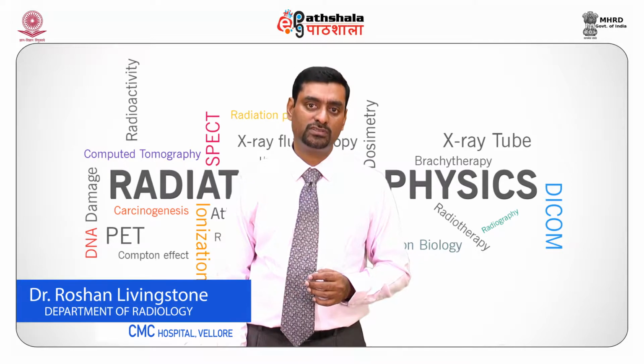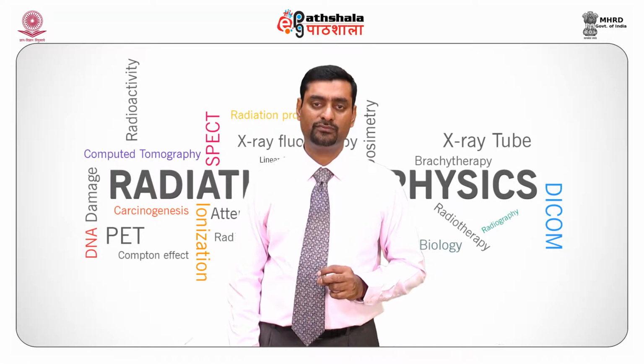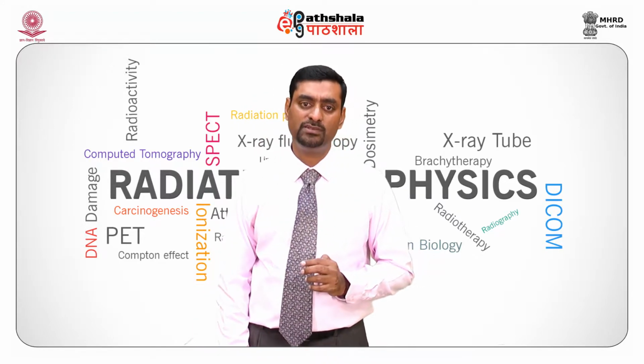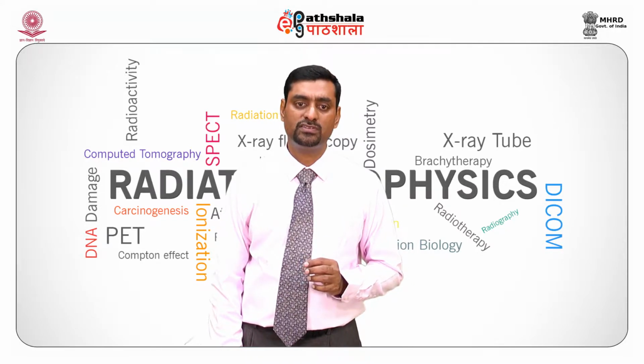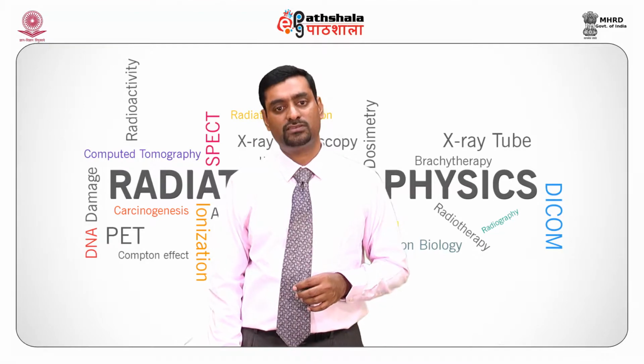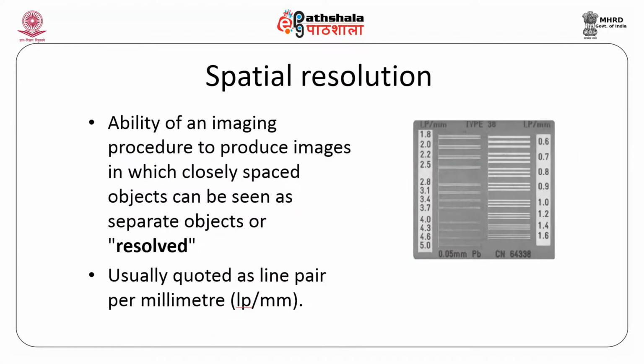Let us move on to spatial resolution. Let us define spatial resolution. Spatial resolution is the ability of an imaging procedure to produce images in which closely spaced objects can be seen as separate objects, or resolved. So in this image you are able to see line pairs at 0.6, 0.7, 0.8, 0.9, 1, 1.2, 1.4 onwards, where we see these lines are distinctly seen.